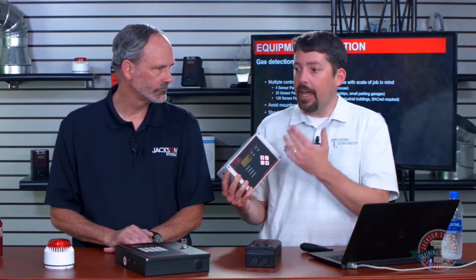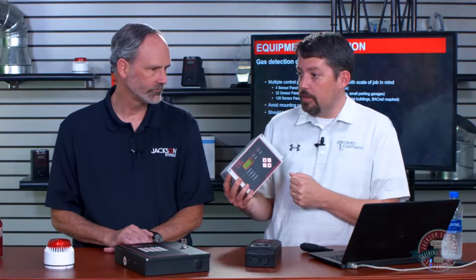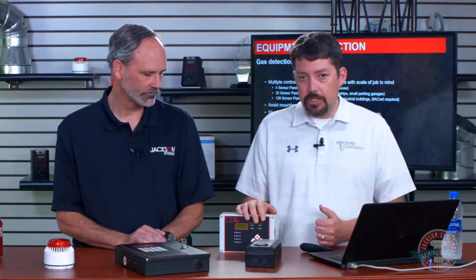Moving on. Gas detection control panels. Multiple control panels should be available from the manufacturer that you're using, and they should be able to scale to the job that you have in mind. As an example, I mentioned we have a 4 sensor panel that we use. A 4 sensor panel meaning I can put 2 CO, 2 NO2 sensors on it, and it's a small application. This is a much less expensive option over having to use a 128 sensor panel and then only using 4 sensors.